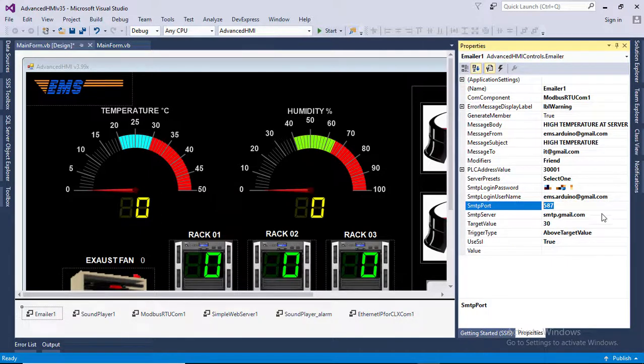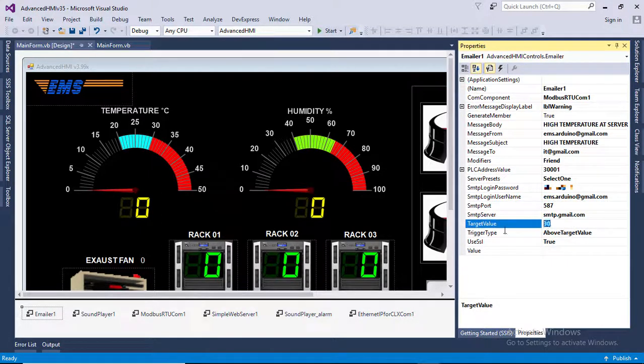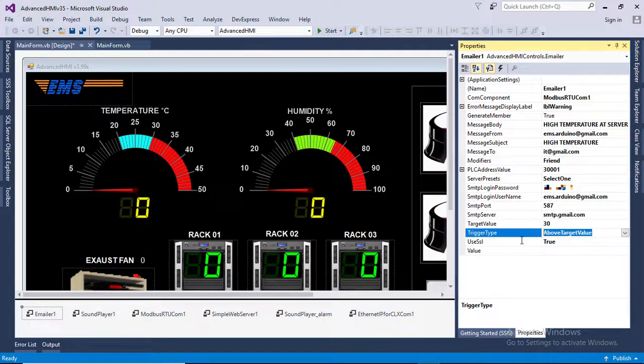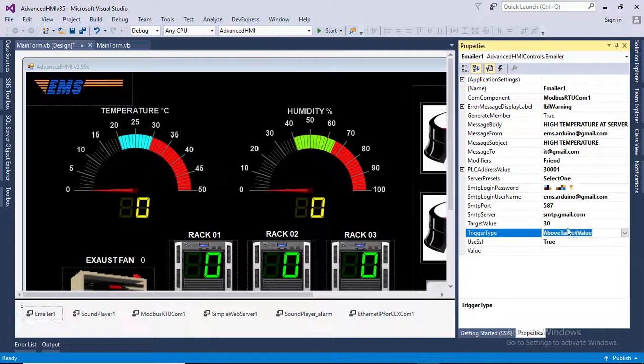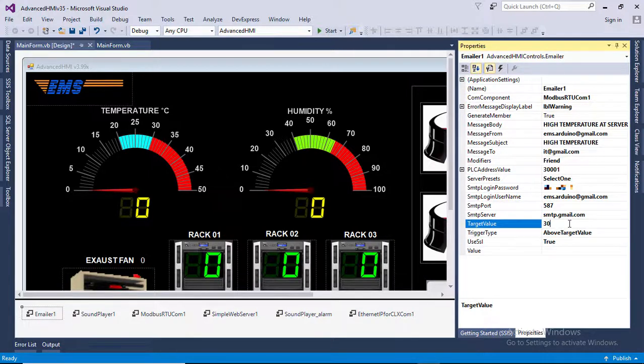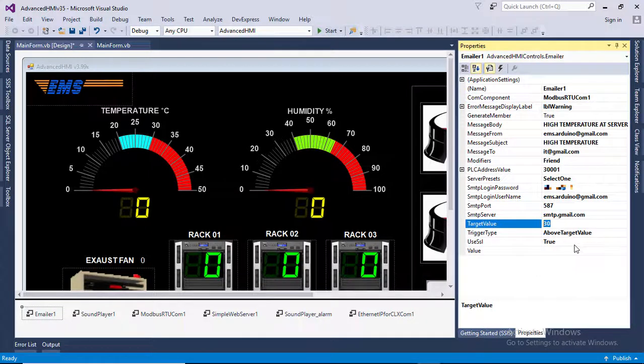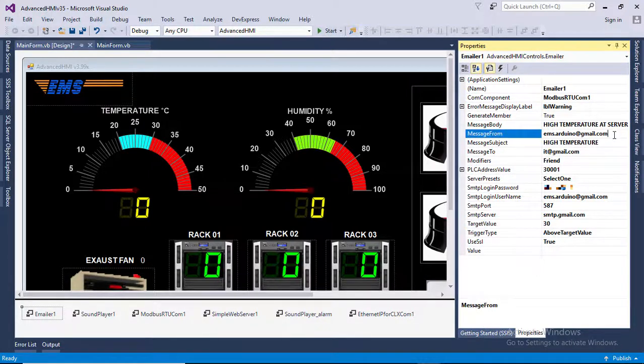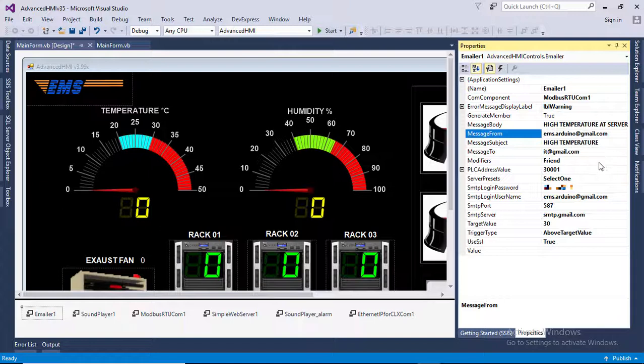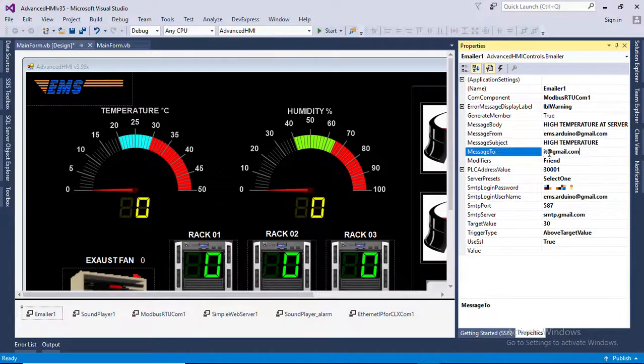Target value is 30. The trigger type is above the target value, which means if temperature rises and crosses 30 degrees, the system will send email automatically to the recipient address. For this case, it is IT@gmail.com.